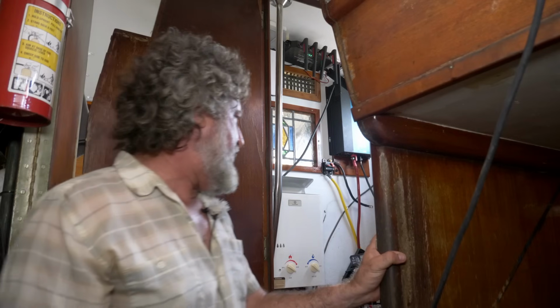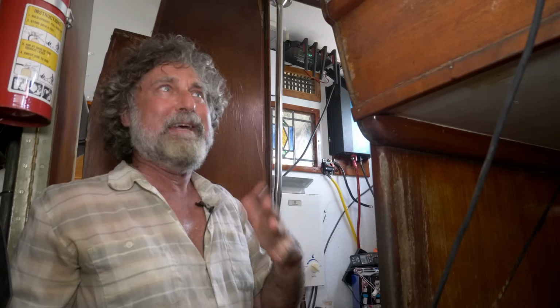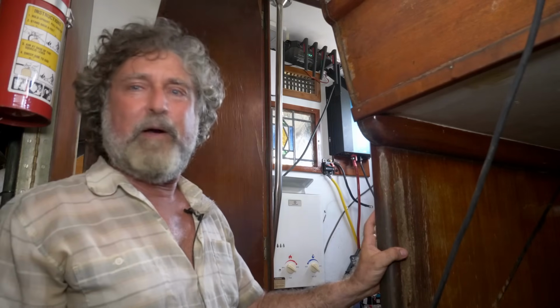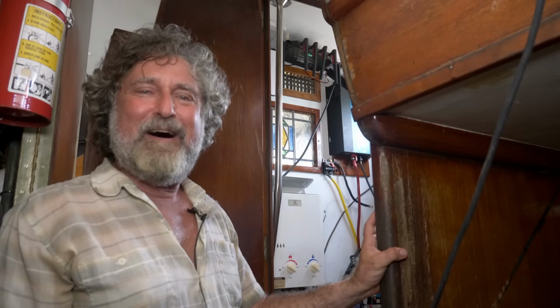Now I've turned it down to 88 amps. That's not because I want to go well below the 100, it's just because I don't have any way of fine tuning - that heat gun isn't that adjustable. But we're going to let it run for quite a while again, looking for heat.